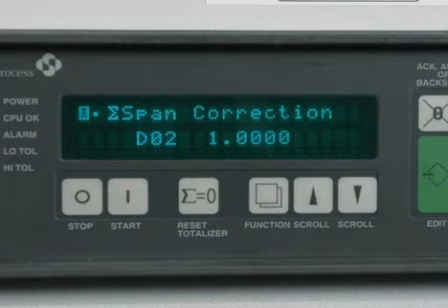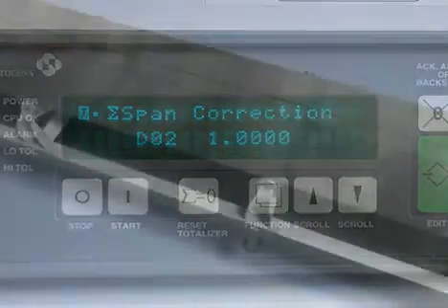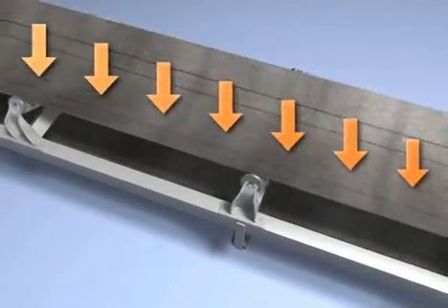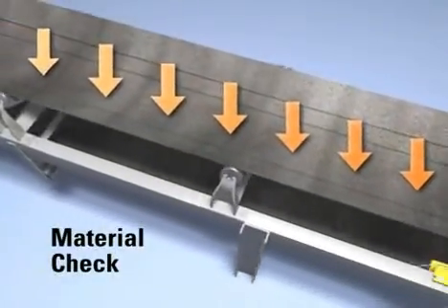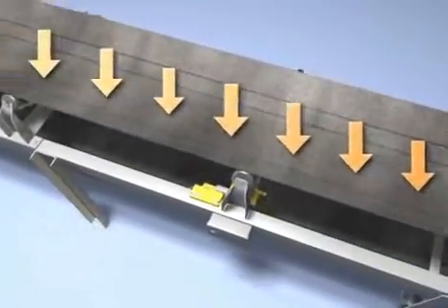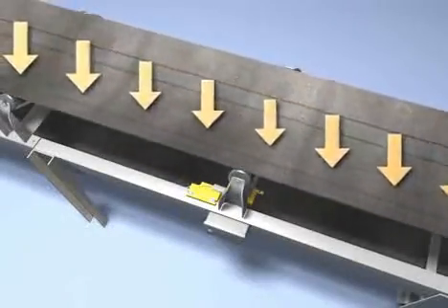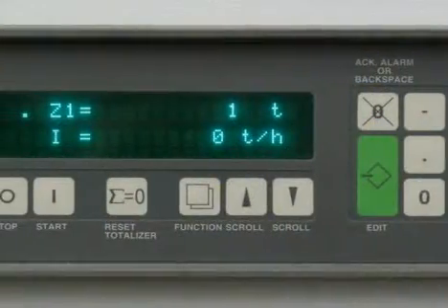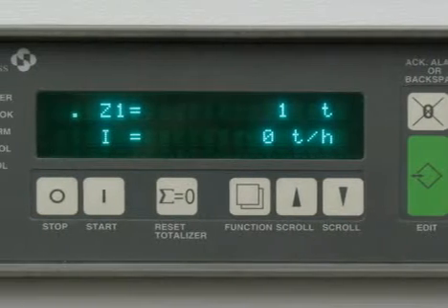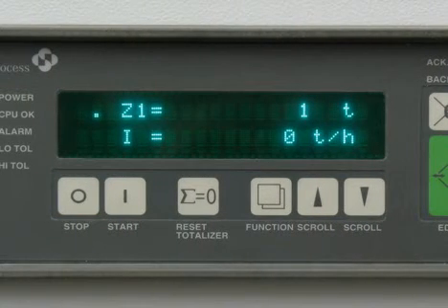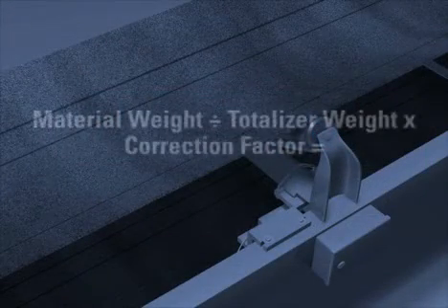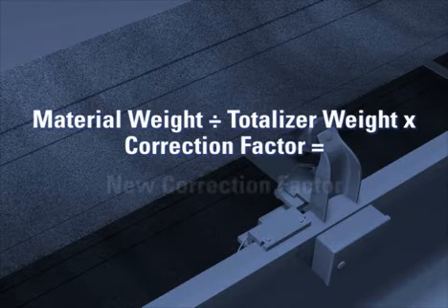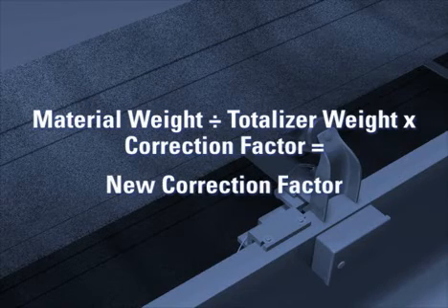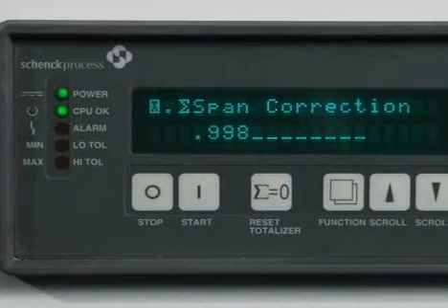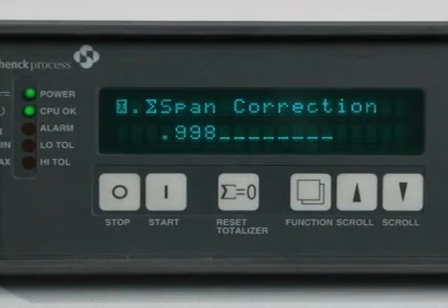If it is possible, finish the calibration process by performing a material check with a volume of material of a known weight. This calibration should run at least 5 to 10 minutes of material at somewhat normal rates. With the system running in totalizer mode, compare the totalized weight on the readout with the actual weight of the material. If there is a difference between the two, use the formula supplied on your calibration instruction sheet to create a new correction factor. Enter the resulting new correction factor to complete the calibration process.